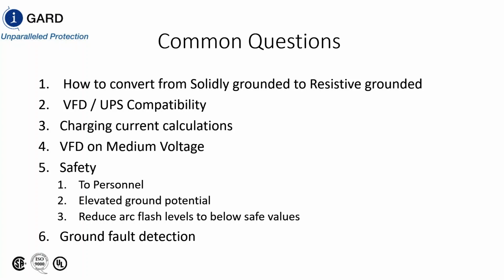Can you discuss the application of HRG on the 480 volt secondary of a Y delta transformer? I'll get that one, Aaron, if you don't mind. With a Y delta transformer, you're obviously going to have to create a neutral on the delta side, and there are many ways you can do that. I assume the delta side is a secondary and the part that you want to put the resistance grounded system on. So you'll have to either create a neutral with a zigzag transformer, a Y grounded delta, or a Y grounded open corner delta, and each one of these will limit the fault current, and you may employ a resistance grounded system at that point and treat it like a Y system.